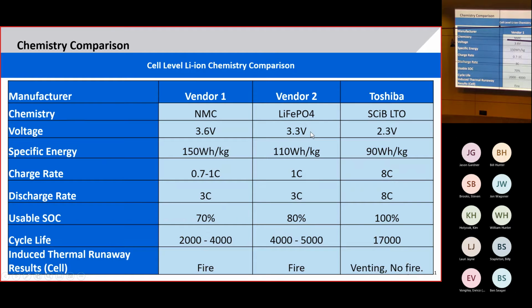Same as VRLA, right? With VRLA, we float them at 2.25, but you can only discharge them to 1.67 or 1.75, depending on the application, so you can't use the other energy there. Same thing for lithium-ion batteries, very similar.